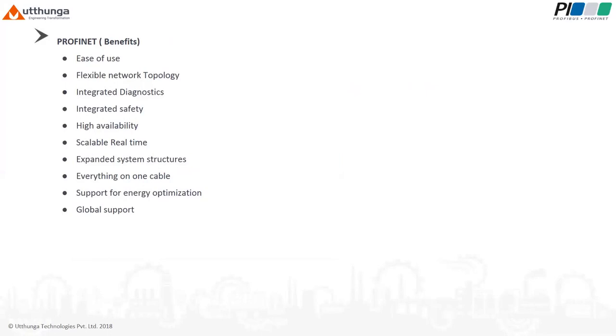Benefits over other protocols. Ease of use. For plant and machine manufacturers, the use of PROFINET minimizes the cost of installation and commissioning. The plant owner profits from ease of plant expansion, high plant availability, and fast and efficient automation. Flexible network topology. Flexible network topology in the sense that it can go up to line, ring, star, and redundant topologies. It's really flexible for PROFINET.